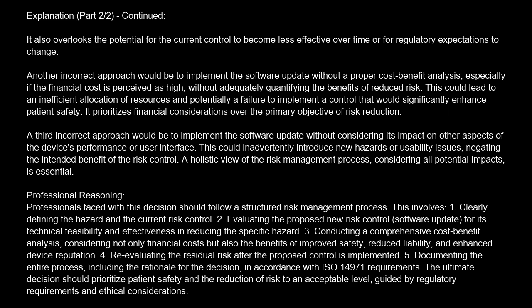Professional reasoning. Professionals faced with this decision should follow a structured risk management process. This involves: 1. Clearly defining the hazard and the current risk control. 2. Evaluating the proposed new risk control software update for its technical feasibility and effectiveness in reducing the specific hazard. 3. Conducting a comprehensive cost-benefit analysis, considering not only financial costs but also the benefits of improved safety, reduced liability, and enhanced device reputation. 4. Re-evaluating the residual risk after the proposed control is implemented. 5. Documenting the entire process, including the rationale for the decision, in accordance with ISO 14971 requirements. The ultimate decision should prioritize patient safety and the reduction of risk to an acceptable level, guided by regulatory requirements and ethical considerations. Question 19.